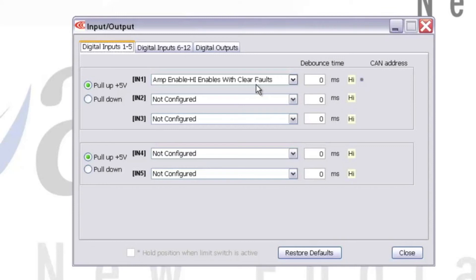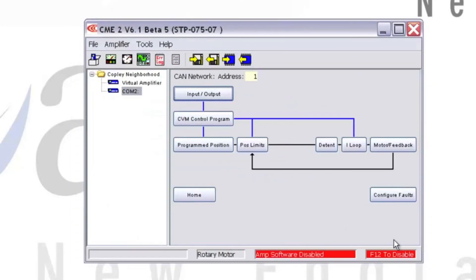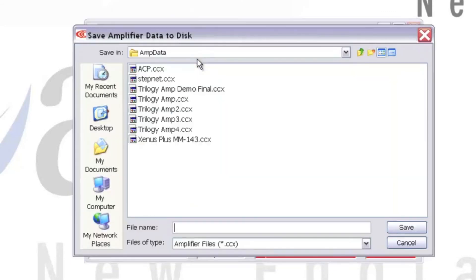This will cause the amplifier to be hardware enabled when Input 1 sees a voltage between plus 5 and plus 24 volts DC. Since we've manually set the input up to be pulled up to plus 5 volts, the amplifier will be hardware enabled throughout the testing process.